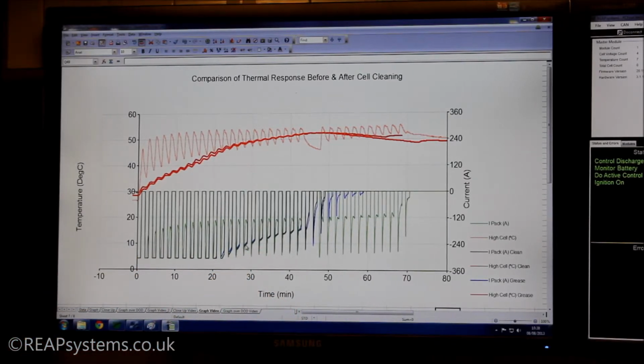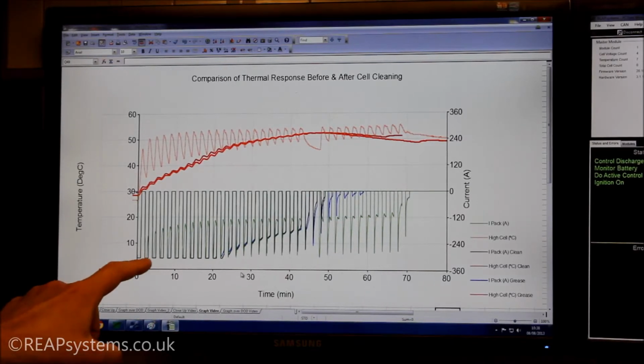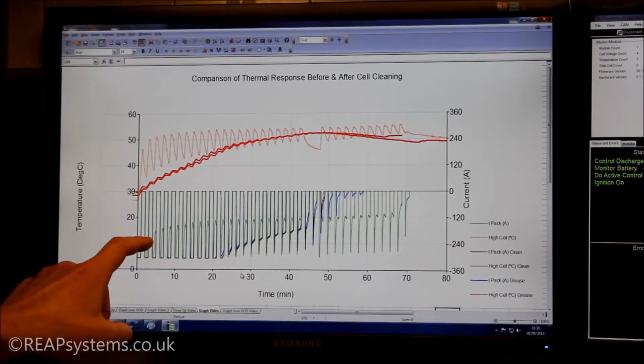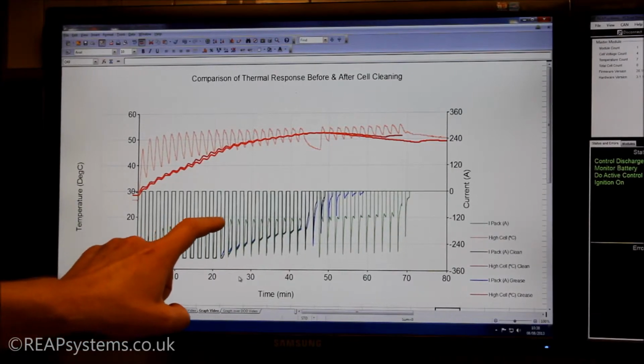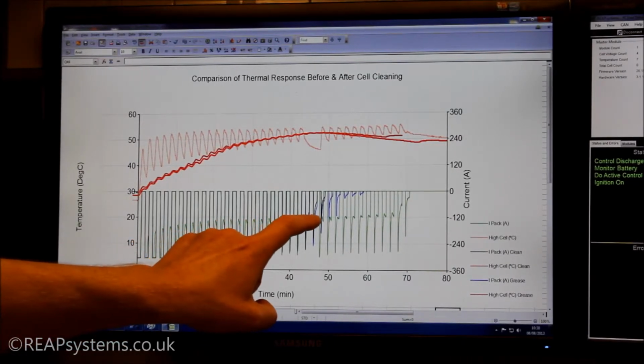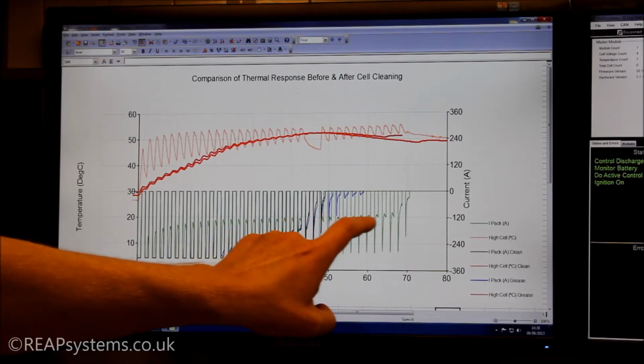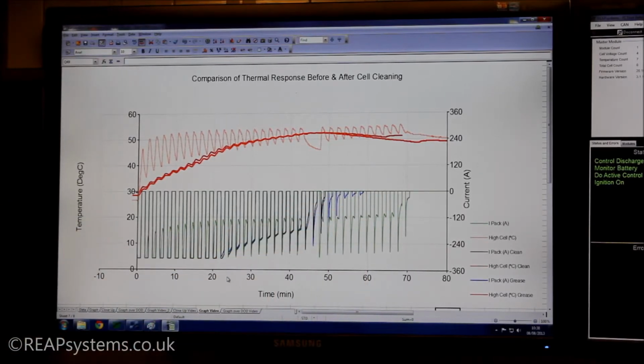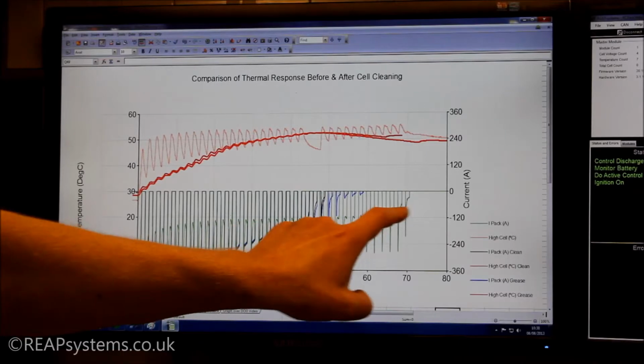Potentially, yes. And if we look at the results without any cleaning, we see there's an immediate reduction, limitation in the discharge current. Which is this here. And we really can't extract much power from the battery due to the high temperature, which means we have a much longer time to discharge the battery fully. It's this bit here.